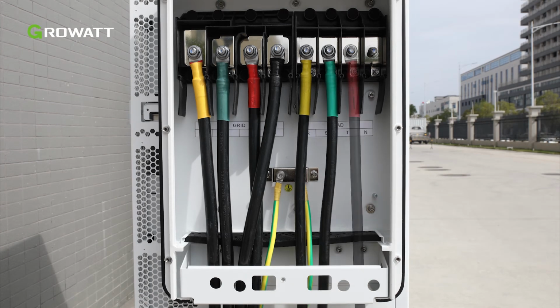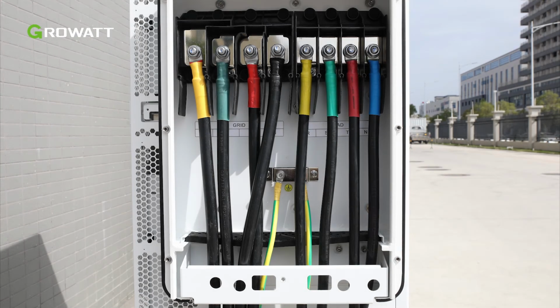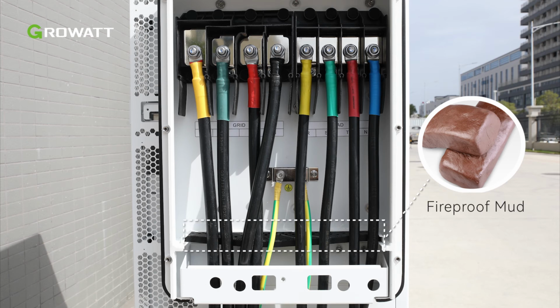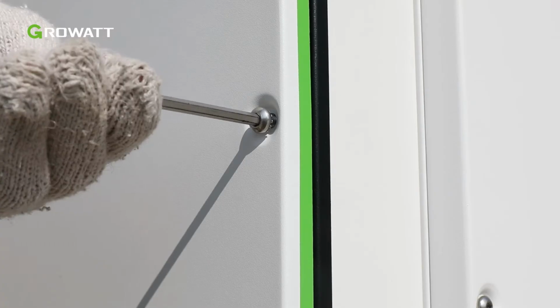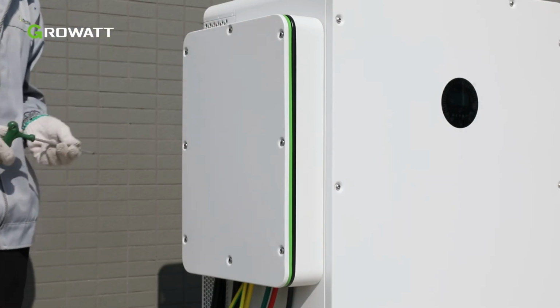After connecting all the cables on the AC side, including main panels, then apply fireproof mud to the waterproof silicone mat at the inlet side. Connect the ground of the box panel. Lock the cover of the AC junction box after the fireproof mud is applied.